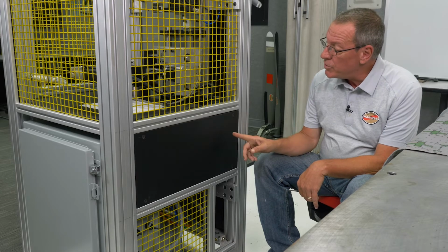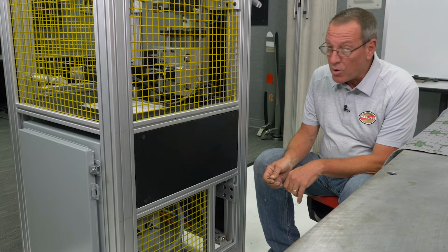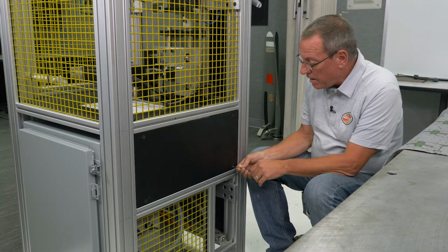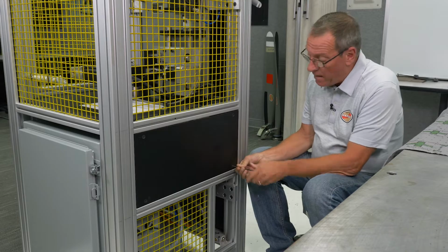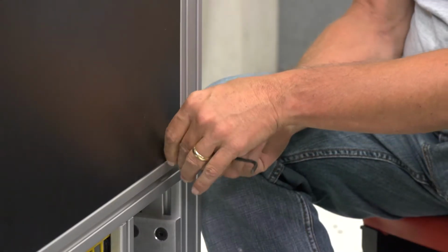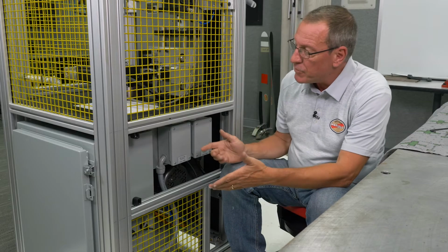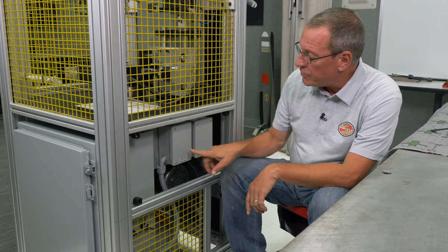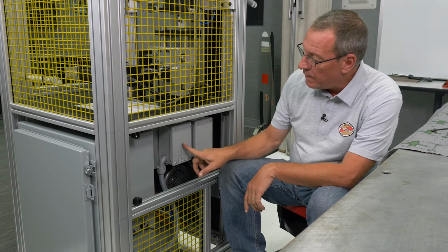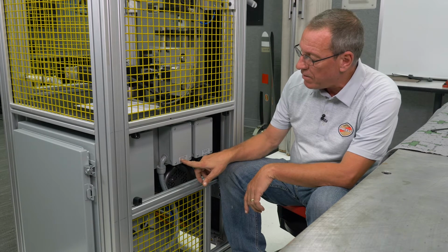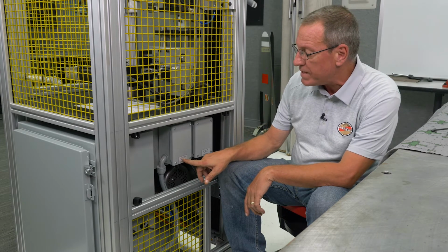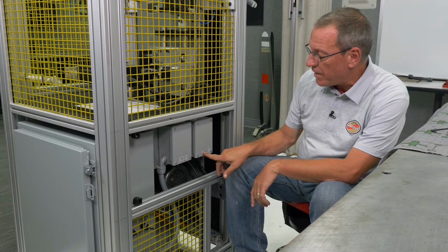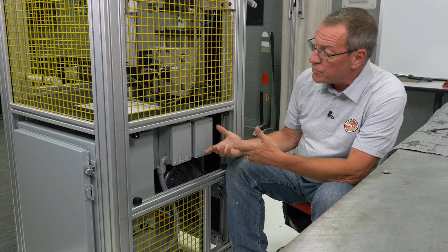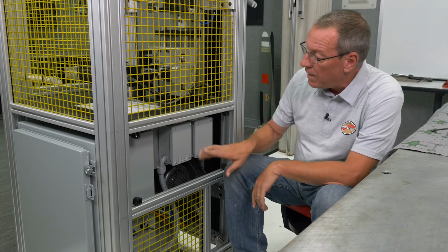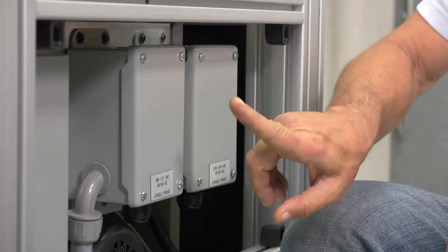The next thing is to access the electrical power connection boxes. And to do that, we need to remove this panel. Once the panel's removed, locate the two power boxes. This box over here is 110 volts to 127 volts. This box over here is 220 to 240. So depending upon your local power supply, you'll either remove the cover from either this box or this box.